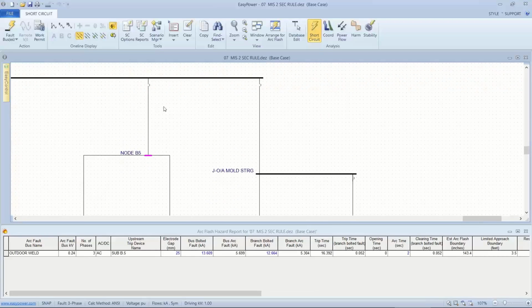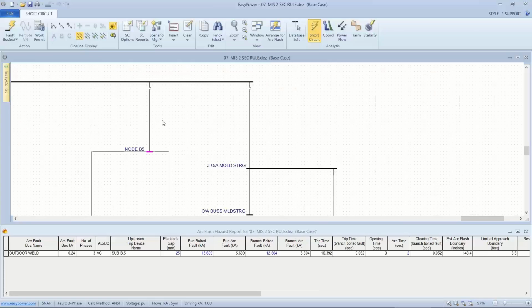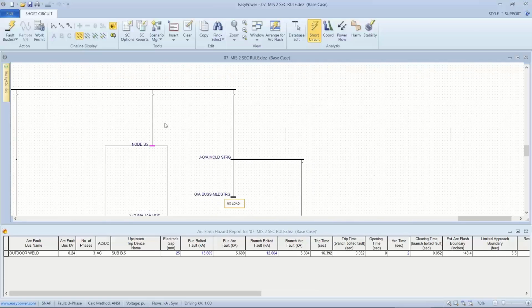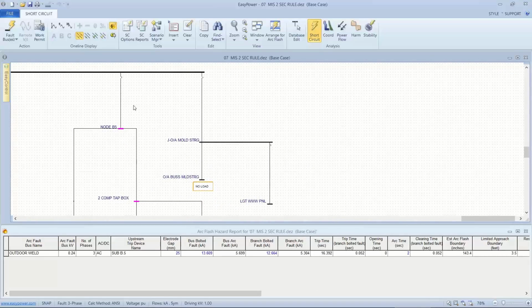So the next step I would take is to ask, does the change to the new standard affect this result? So let's go back to my short circuit arc flash setup. Let's select 2018. Let's exclude the main. Let's go ahead and leave the 2-second limit in there for now. Let's use the integrated method. Let's apply the results and see what happens.